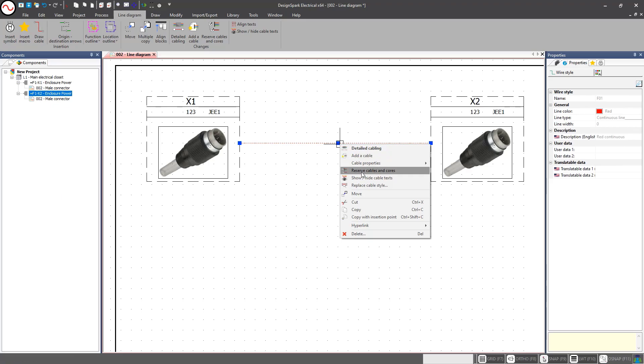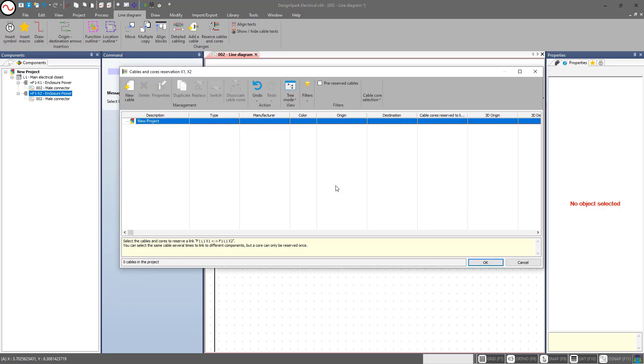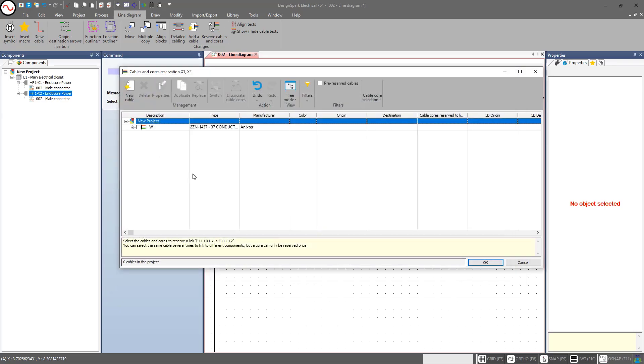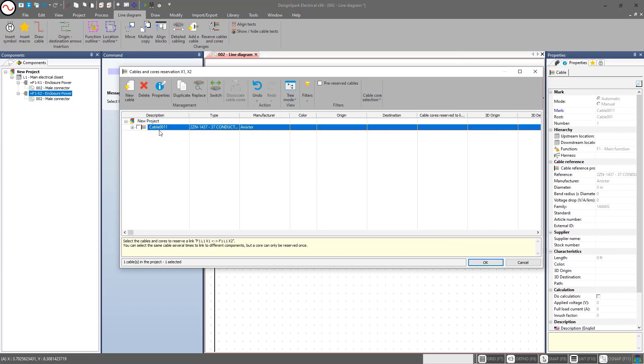In order to add information to this cable, we need to add cable properties and reserve cable cores. I've already added a cable to this project previously, but I'm going to delete that and start over. Just as we have a symbol library, manufacturer part library, and title block library, we also have a cable library. I need to define which cables from that library belong to this project, so I'll select 'new cable,' pull a cable from the library, and add it. Just like that, I now have W1 — I can rename it to 'Cable 001' if needed.